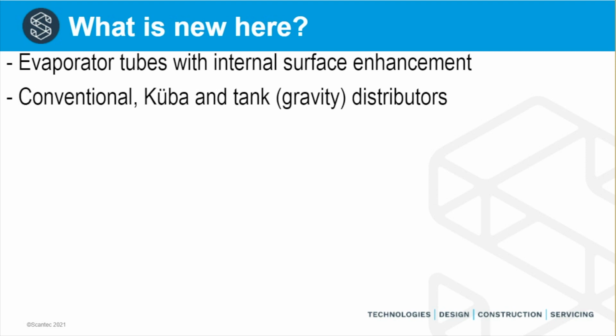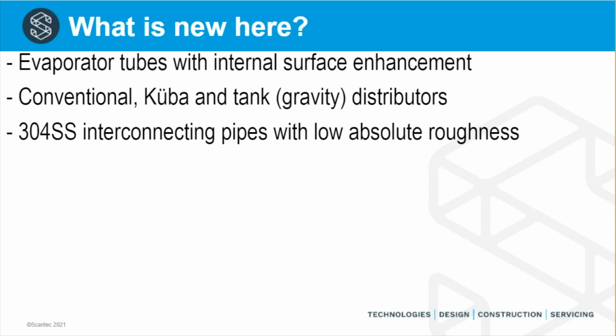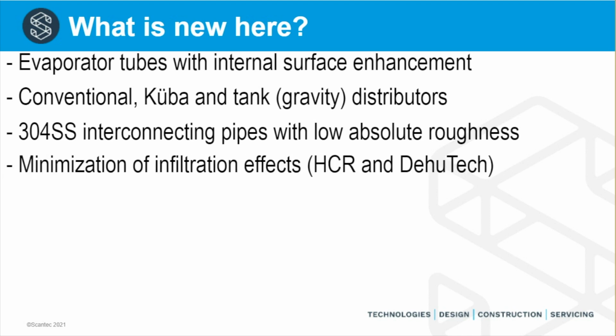We discussed the tank distributors. Interconnecting pipelines within the plant: these days, it is customary to use 304 stainless steel tubes for the interconnecting pipelines, so those pipes that interconnect compressors, vessels, condensers, etc. These have an absolute roughness, which is measured in meters, that is somewhere between 20 and 40 times lower than it is for carbon steel tubes. So this gives rise to a significantly lower pressure drop. Now, that significantly lower pressure drop does not translate into a great improvement in energy efficiency, probably somewhere between 2 and 4%. But the energy efficiency improvement in these types of plant is not one big thing. It's a matter of combining a lot of little things to a big achievement at the end.